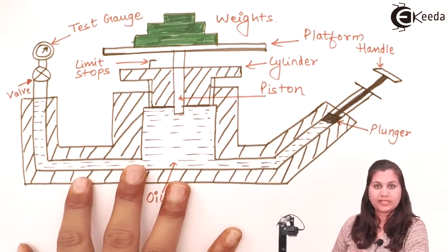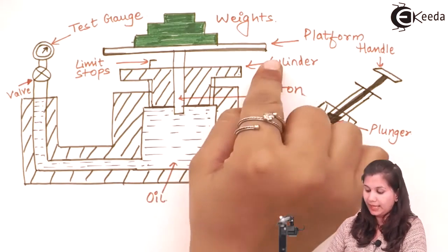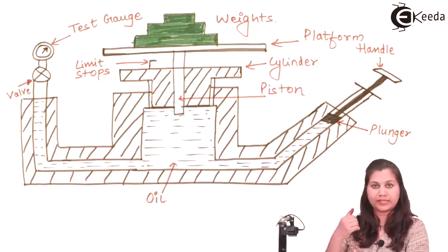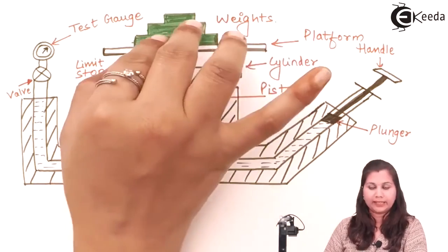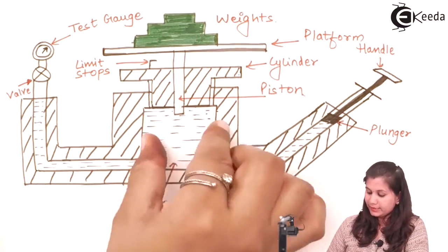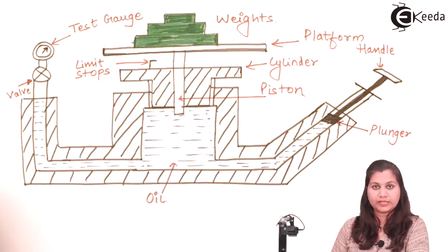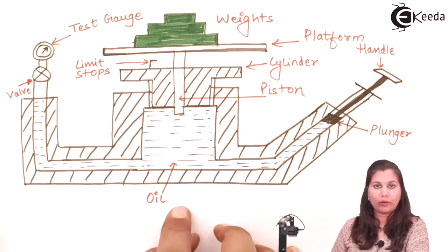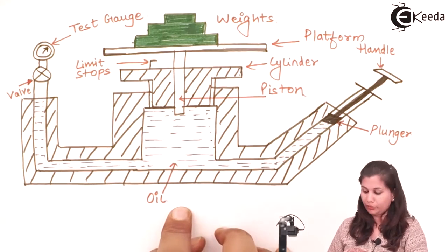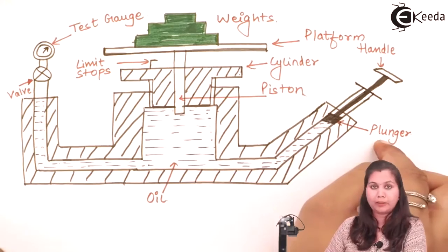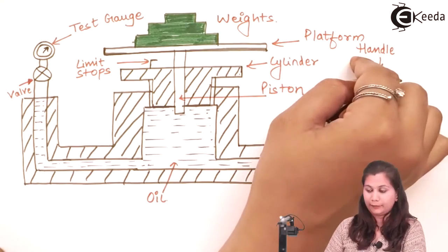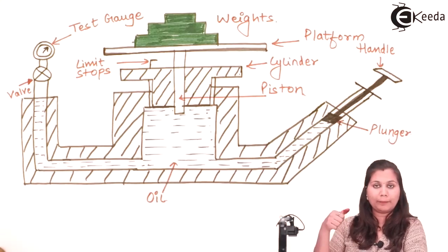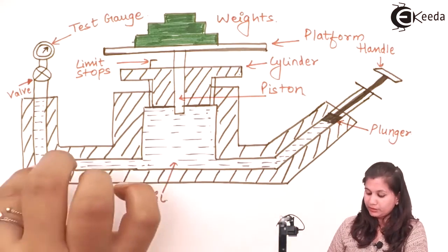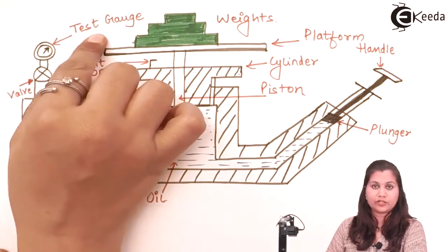So this is the diagram for the deadweight tester. Here you can see that it consists of the piston and the cylinder. Inside the cylinder we have the piston fitted inside it, and on the piston we have a platform over which the weights are kept. Now this is the chamber. The piston is fitted over this chamber. In this chamber we have oil which is free from impurities, and on the other side we have the plunger. This plunger is attached with the handle. This plunger and handle assembly is used to apply the pressure inside this chamber. To the other end of the chamber, the valve with the test gauge, the gauge which we want to calibrate, is attached.